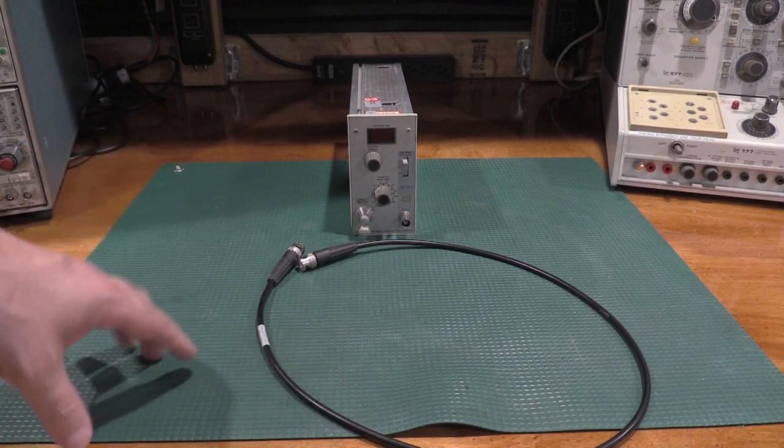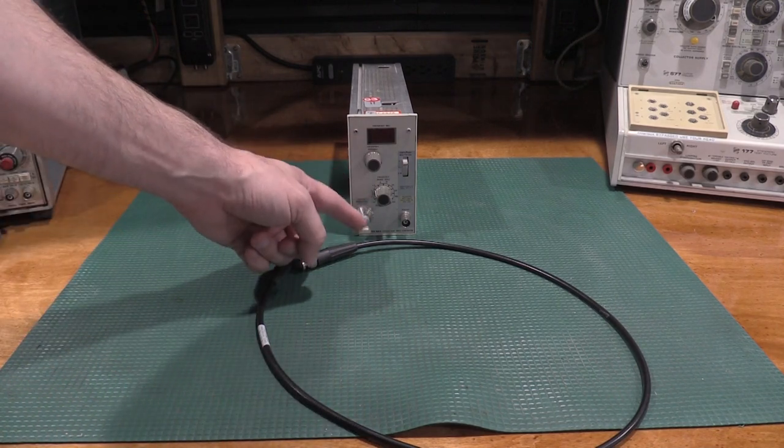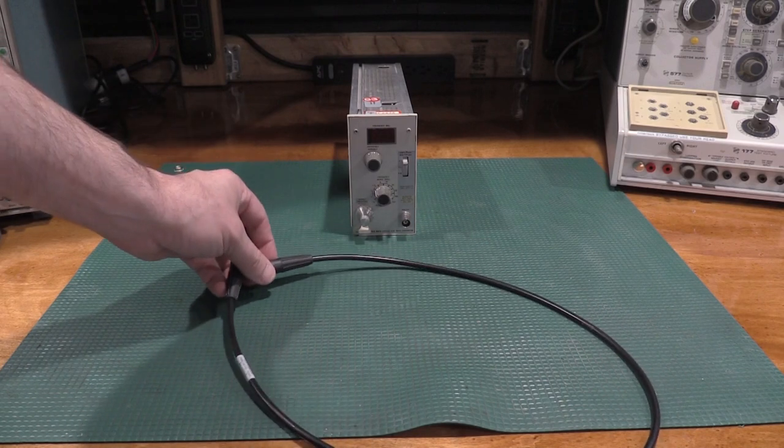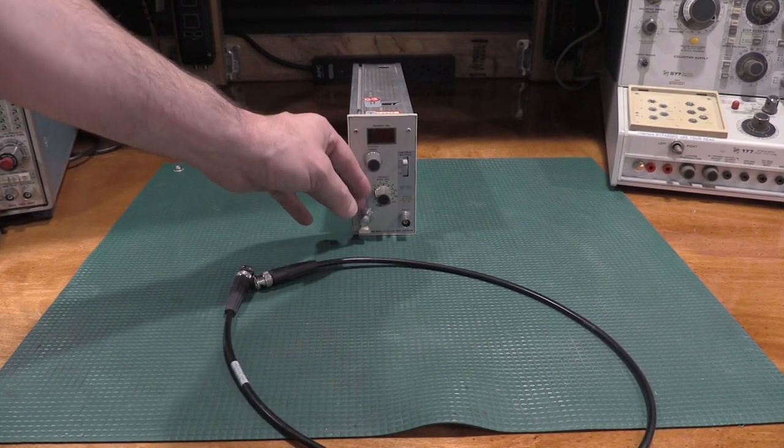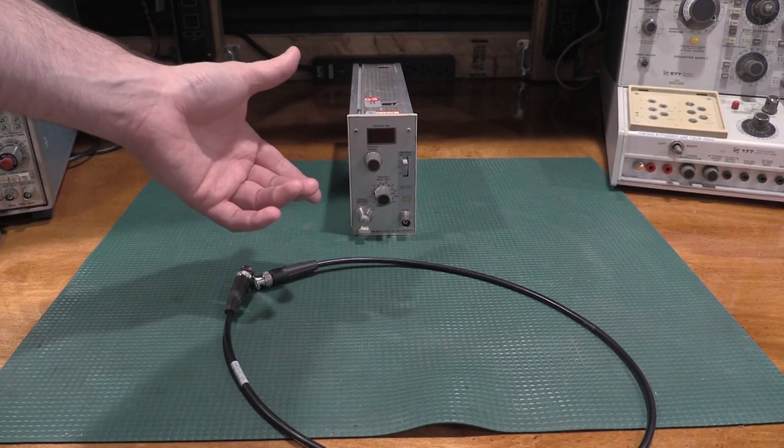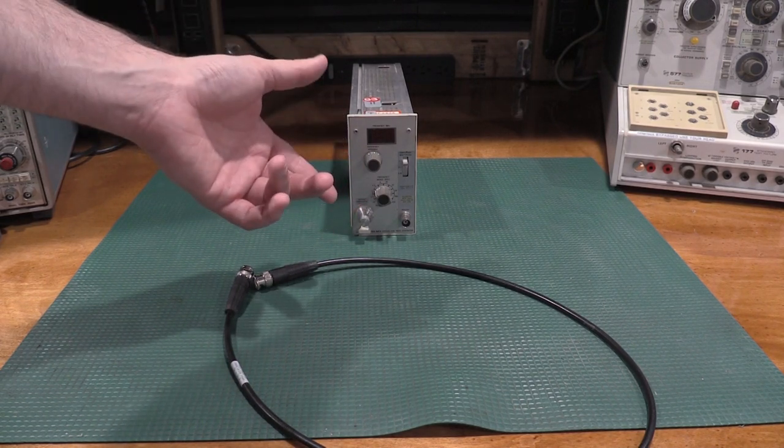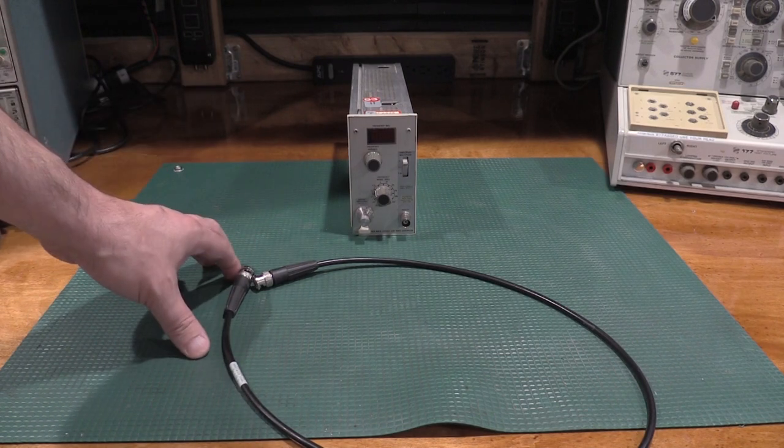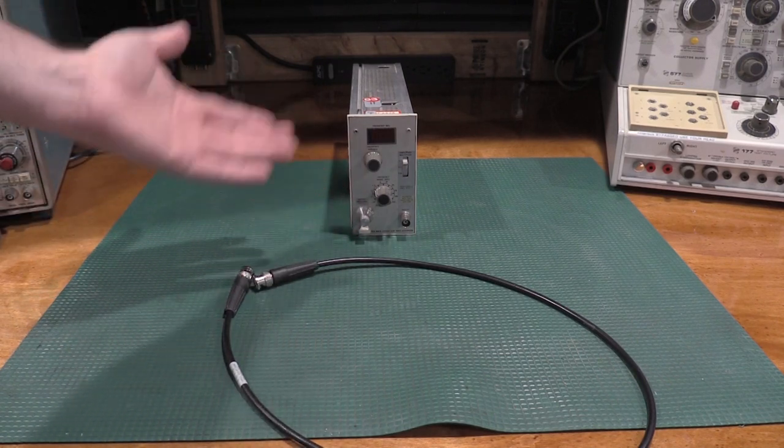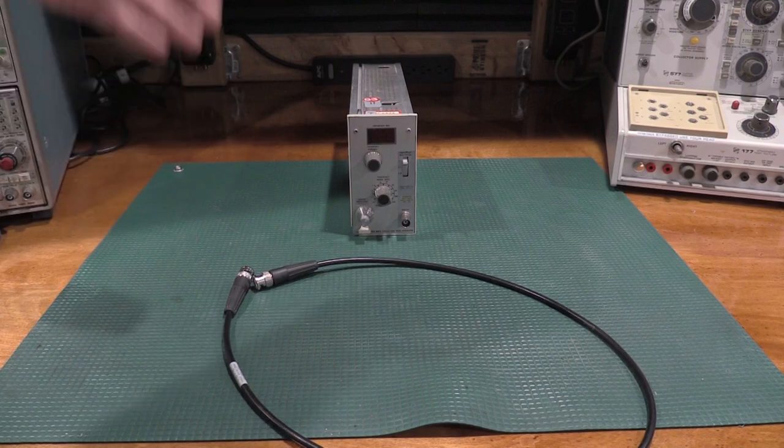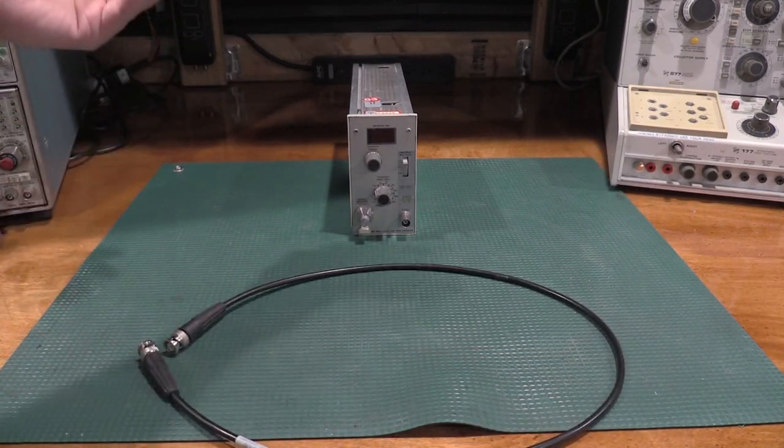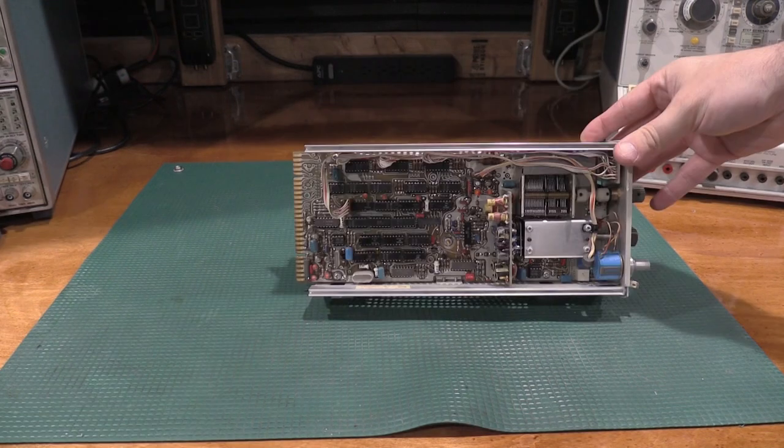If you need the absolute voltage accuracy out of the SG503, yes, the cable matters. If you need just the leveling function of having it be the same amplitude over frequency, no, not really. Because you don't care what the absolute is. You just care that it stays the same. So your measurements will vary. Do you need this cable? All depends on what you're planning on doing.